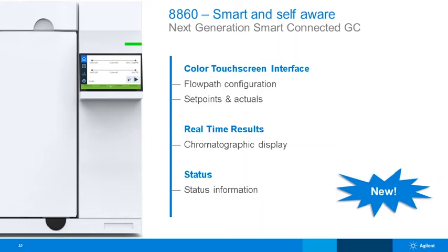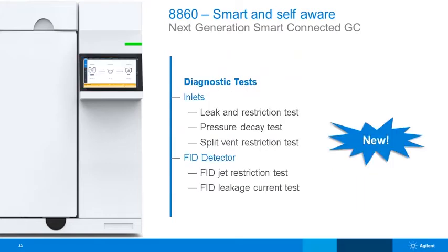So the 8860, this is what the touchscreen looks like. It's very similar in its appearance to the Intuvo, so it's a color touchscreen interface. It's like you get on your phones, so it's incredibly responsive. It's not squidgy, it's a proper touchscreen. On the top there, you see a flow path configuration, and it tells you what the set points are and what the actuals are. And next, if you go down from there, you see the real-time results, a chromatographic display, and then there's also status information should you want to monitor any particular temperature setting.